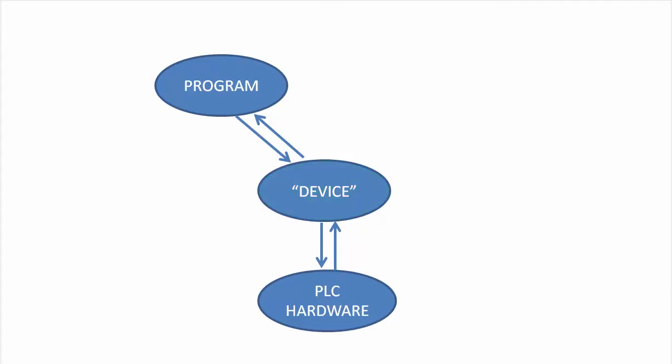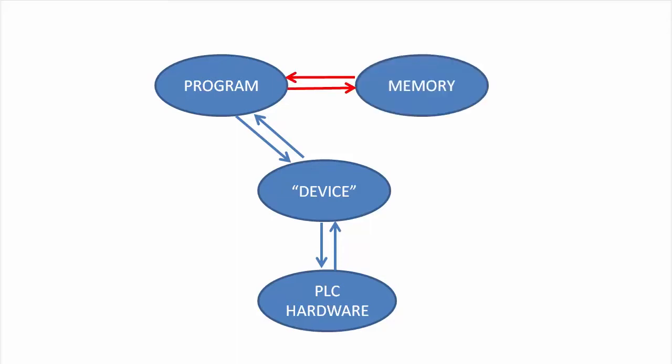That's the power of this device-centric model. Now, most instructions don't need devices, like reading or writing directly to I/O. But even in that case, the program still doesn't talk to the hardware. It writes to memory, which is mapped directly to hardware through a device. So the key takeaway here is only devices talk directly to the hardware, which is why we say that DoMore PLC is device-centric.